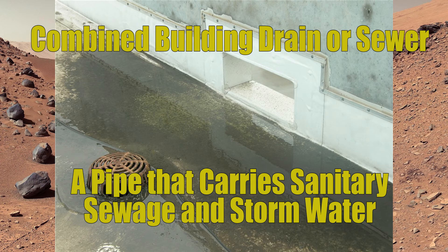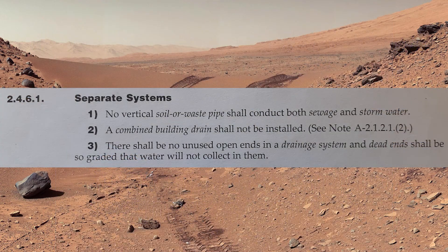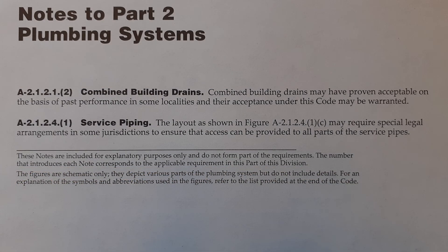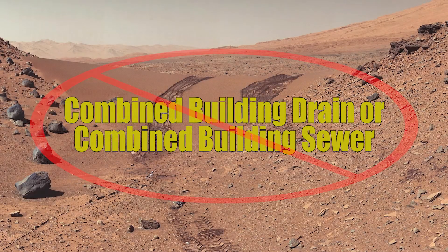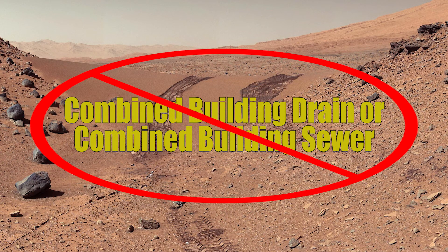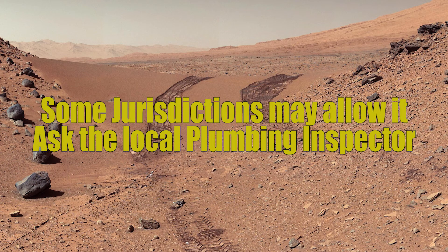The plumbing code does have something to say about combined building drains. Clause 2461, part 2: a combined building drain shall not be installed. There is however a note — A21212 — which says combined building drains may have proven acceptable on the basis of past performance in some localities, and their acceptance under this code may be warranted. In short, installing combined building drains is prohibited, with the exception of some communities that will allow it. The only way to find out whether you're allowed to install one is to talk to the authority having jurisdiction — that would be the local plumbing inspector.